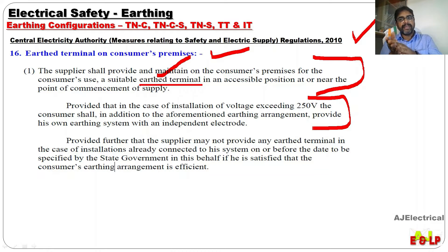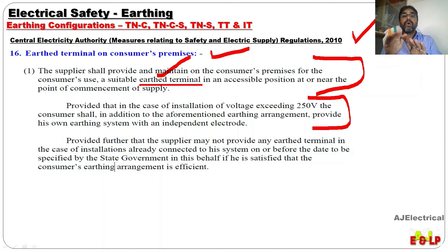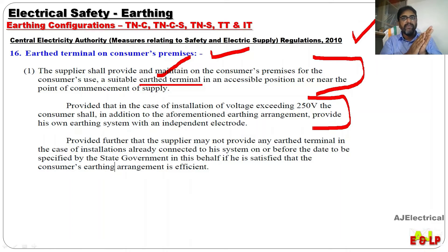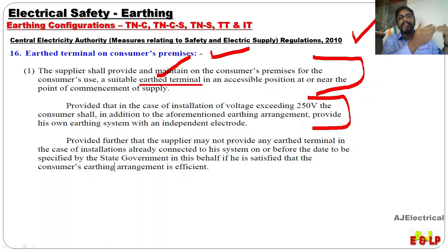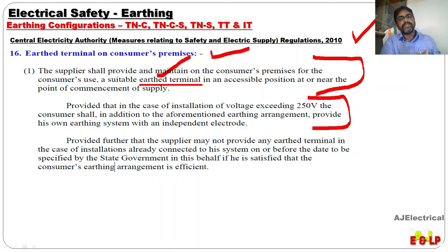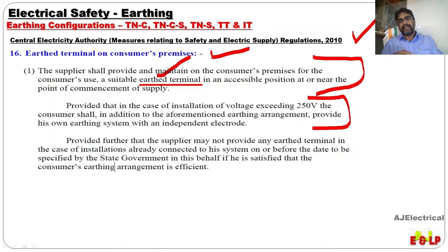Means for those having voltage below or equal to 250 volt, they don't need to have independent earthing — so a single phase consumer is not compelled to have their own earthing arrangement. The earthing given by the supplier is enough. But for three phase consumers, in addition to the earthing given by the supplier, they must have their own earthing arrangement.